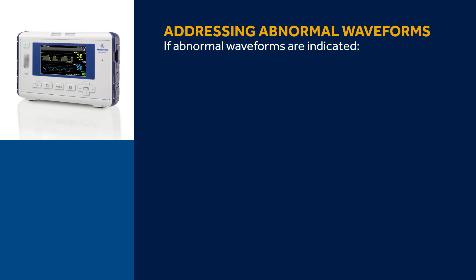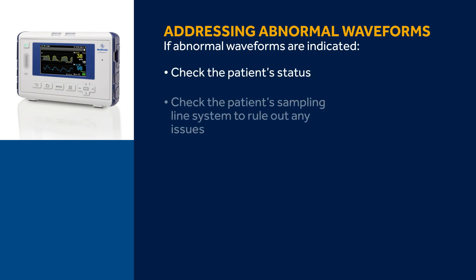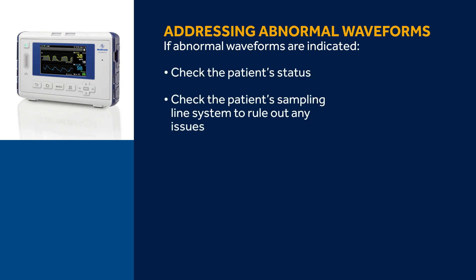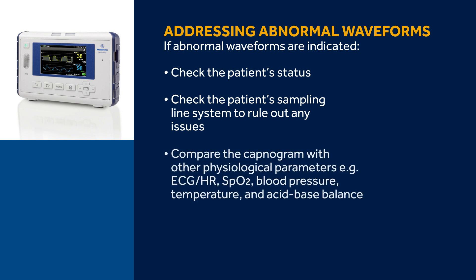If abnormal waveforms are indicated, the following steps are suggested: check the patient's status, and check the patient's sampling line system to rule out any issues such as kinking. It's important to note that correct interpretation of the capnogram can only be achieved by comparison with other physiological parameters such as ECG/HR, SpO2, blood pressure, temperature, and acid-base balance.